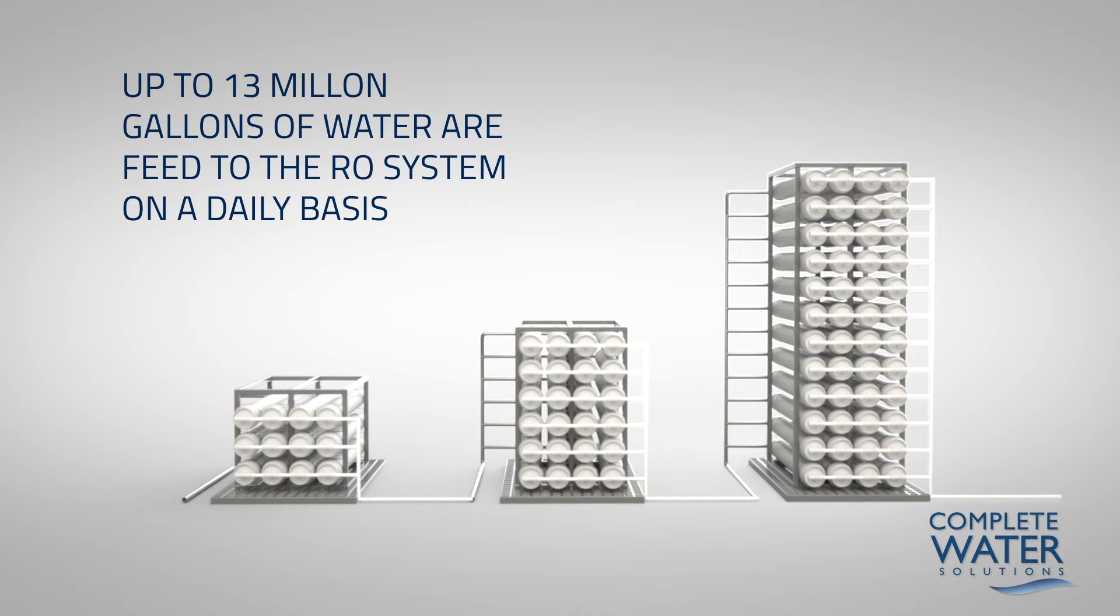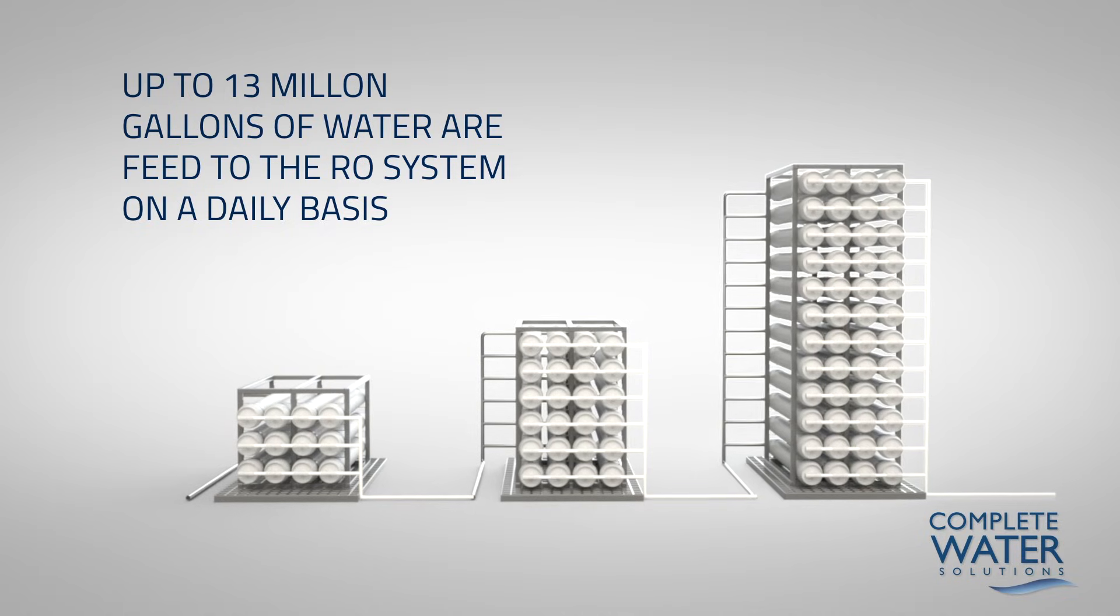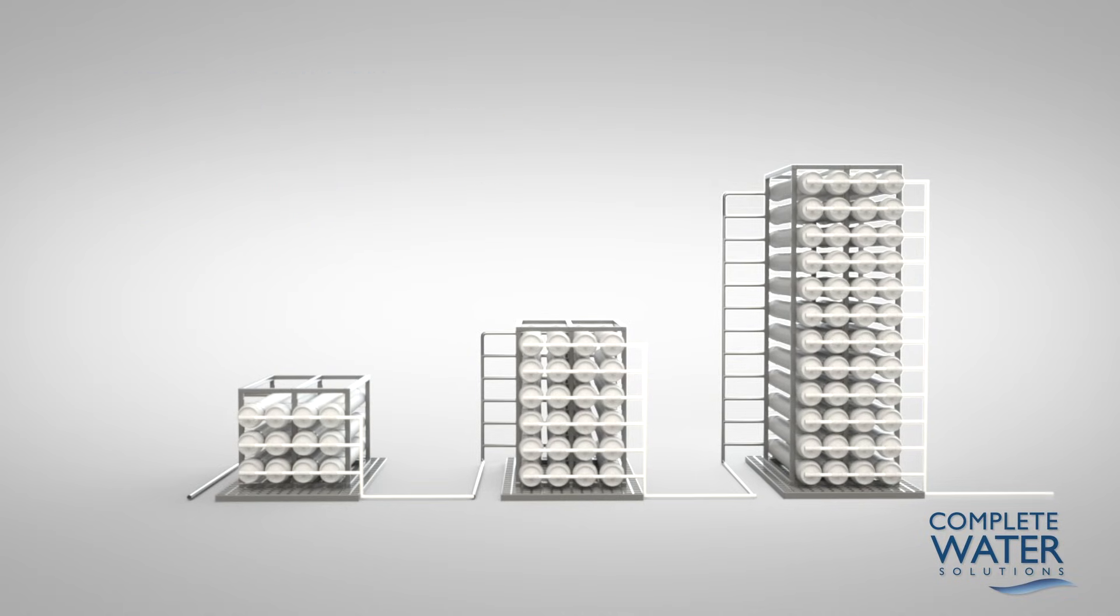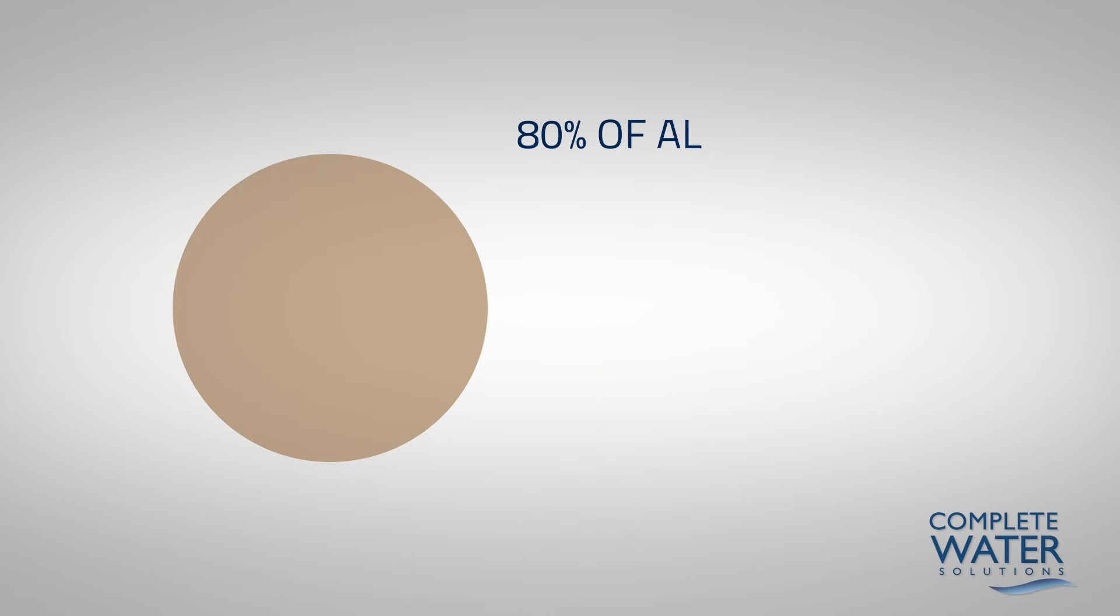Up to 13 million gallons of water are fed to the reverse osmosis system on a daily basis. As the feed water passes through each stage, more reverse osmosis permeate water is extracted. 80% of all feed water is recovered as permeate, reverse osmosis water in this example.